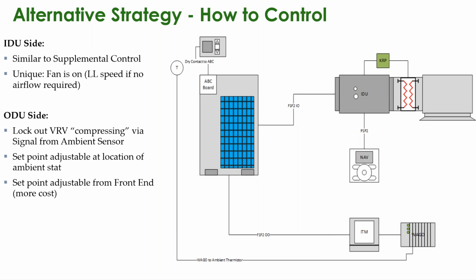On the outdoor side, it varies from manufacturer, but there's various ways to switch that unit off, either built into the logic, or adding external boards with dry contacts that signal from an ambient sensor. You can adjust that set point locally, or you can also adjust it from the front end with a central control system with most manufacturers.